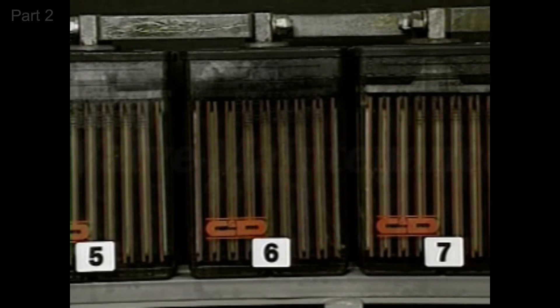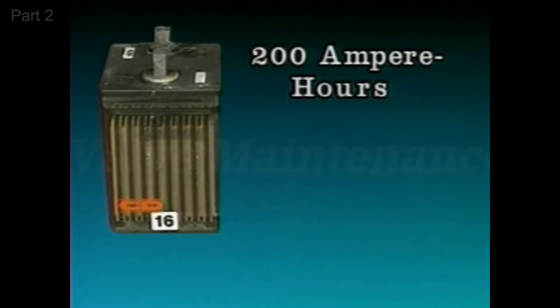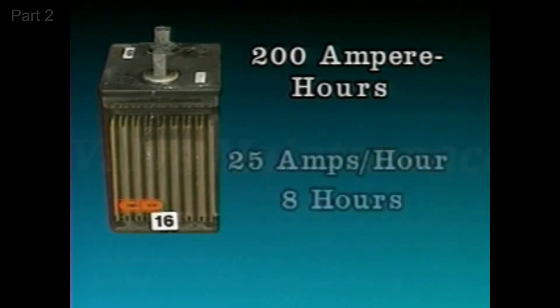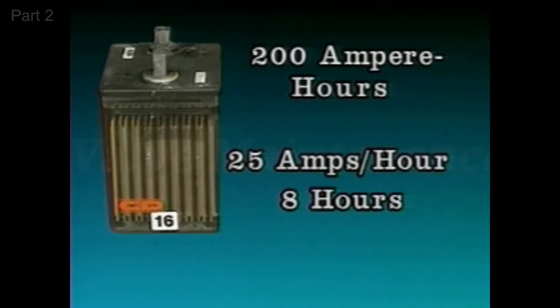Manufacturers typically rate cells based on an 8-hour rate of discharge. For example, this cell is rated at 200 ampere hours. This means it should be able to supply 25 amps of current per hour continuously for 8 hours, for a total of 200 ampere hours.